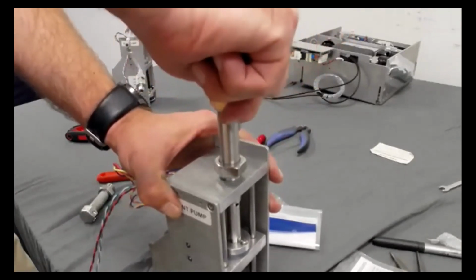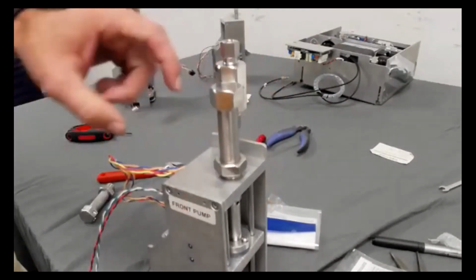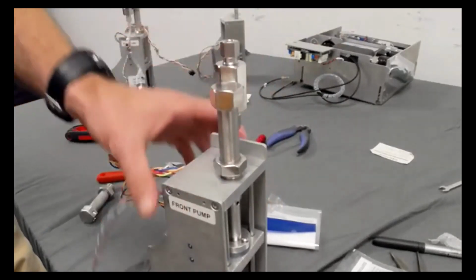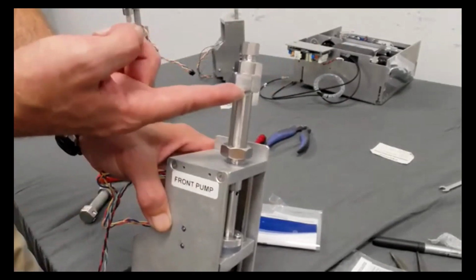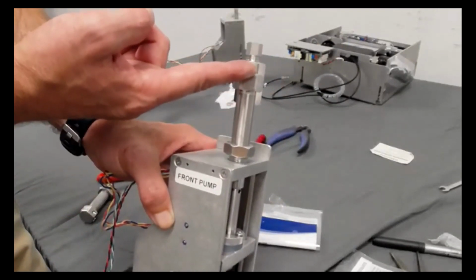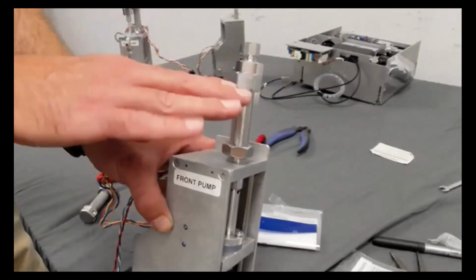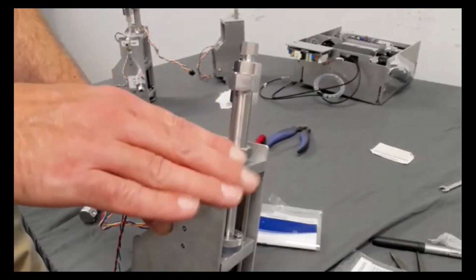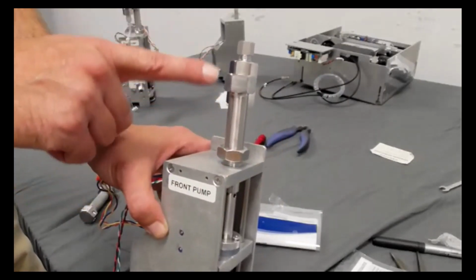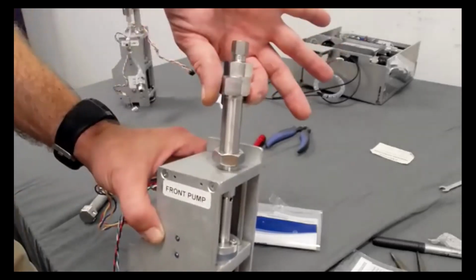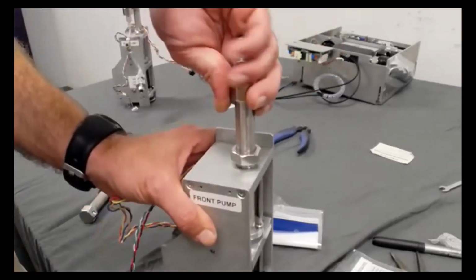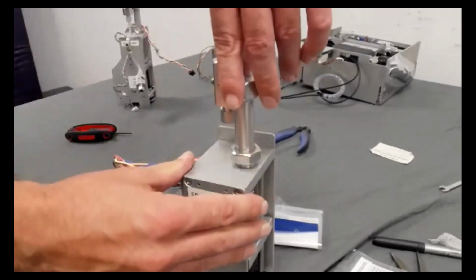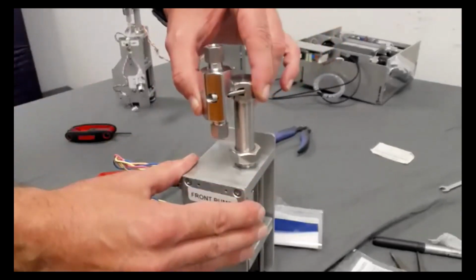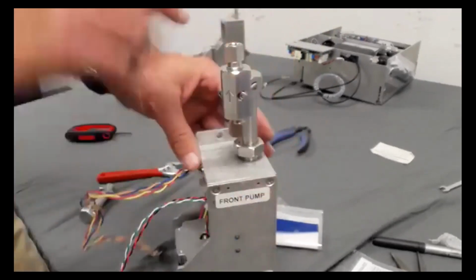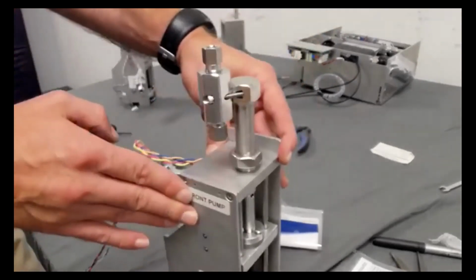So I'm going to take it down by hand until I feel it top out right there. I can feel it. So right now, the top of the piston is hitting the cylinder. So I know my dead volume is 0 right now. But what I want is the cylinder with the check valve housing facing forward. So I'm going to back off. I'm going to loosen it until I get that check valve housing at that nice diagonal from the front.